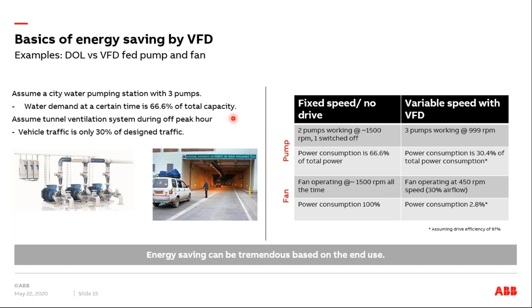In that case, if you had a fixed speed system, with the motor directly connected to the line, you would switch off one of the motors, so you have two pumps running. You'll provide the required flow with two pumps, and your power consumption will be around 66.6%, because you are operating two motors at the rated speed.